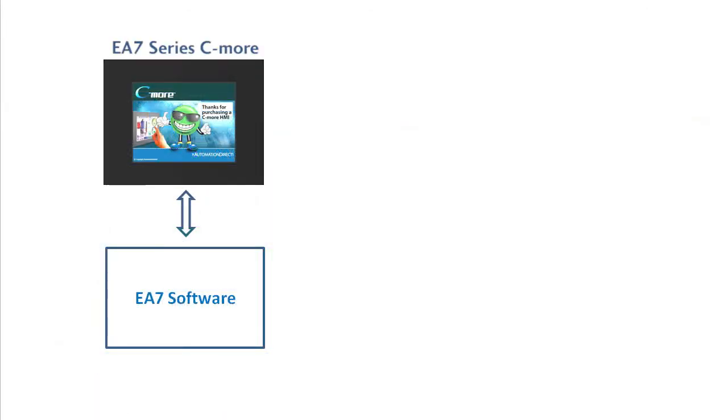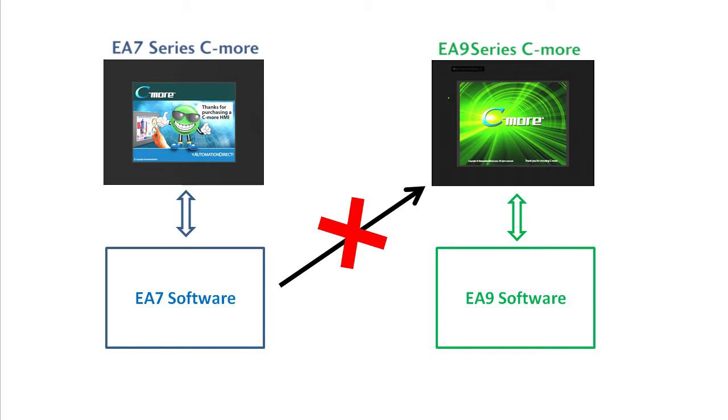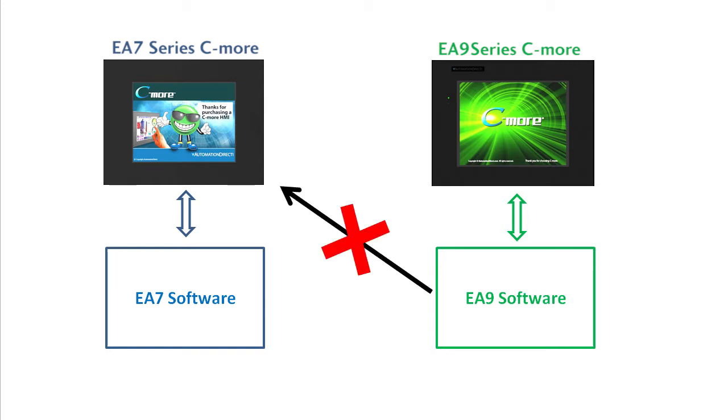It's important to understand that while the software for the EA7 and the EA9 have the same functionality and look exactly the same, they run on completely different processors. Which means the EA7 software doesn't talk to the EA9 panels. And the EA9 software doesn't talk to the EA7 panels.